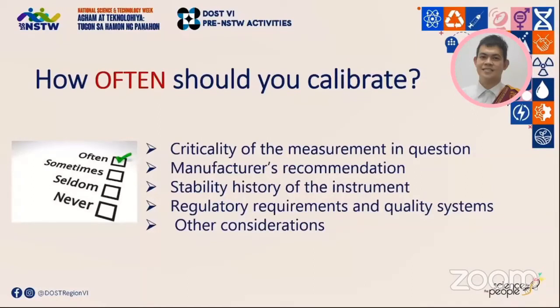There are also regulatory requirements and quality systems. Requirements on calibration vary depending on the industry. For example, the Department of Energy requires petroleum product haulers to have their vehicle tankers calibrated annually. The Consumer Welfare Act states that all instruments for determining weights and measures in consumer transactions shall be tested, calibrated, and sealed every six months by the official sealer — the provincial, city, or municipal treasurer or authorized representative. Other considerations such as frequency of usage and how operators take care of equipment are also things you have to take into account.